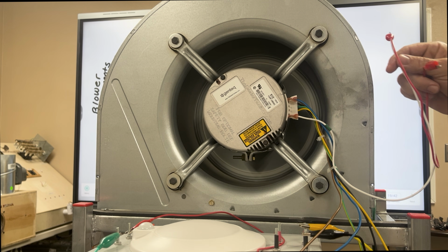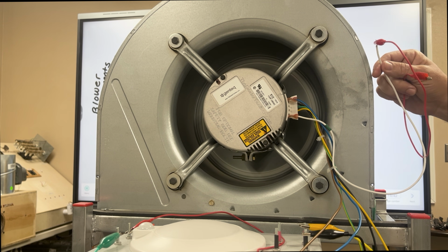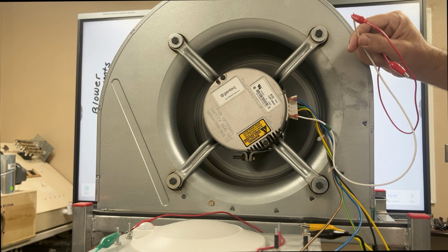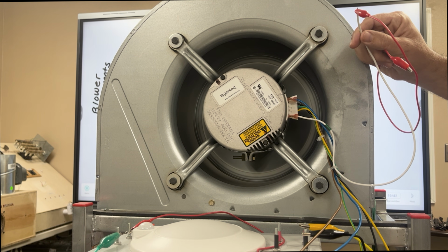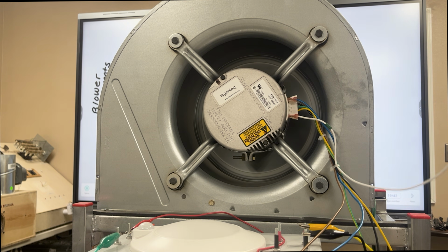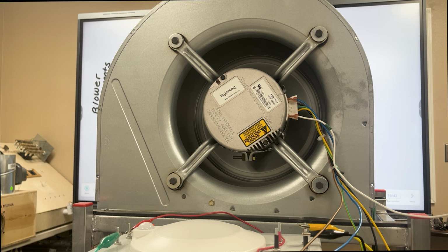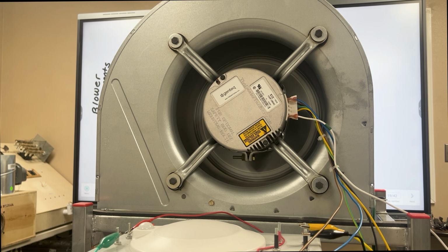I'm going to show you with my timer what the off delay is once we remove power on terminal 1. And once we remove that, you're going to see a 90-second, or a minute and 30 seconds, delay. And that 90 seconds is going to be your off delay. Now, we talked a lot about off delays and why they're important. And it's the same thinking. And when we get to the smart board, we'll talk a little bit more about that.